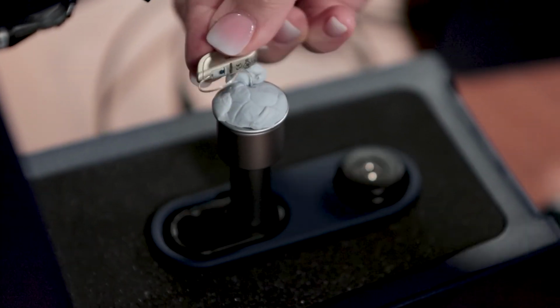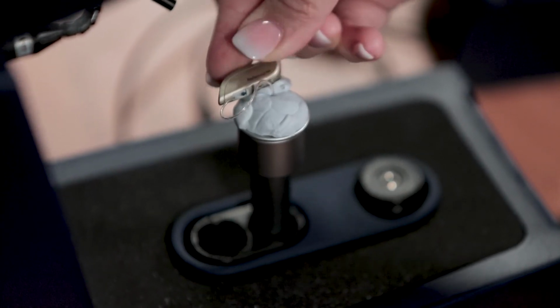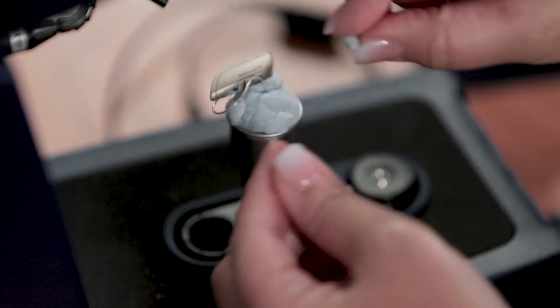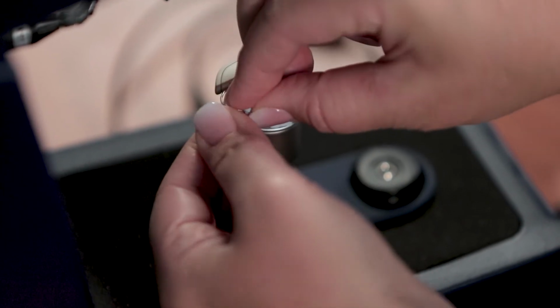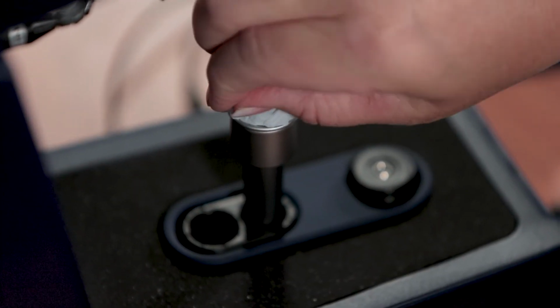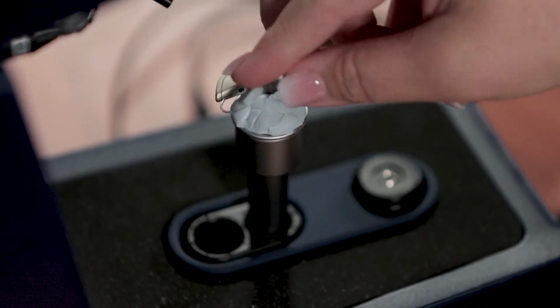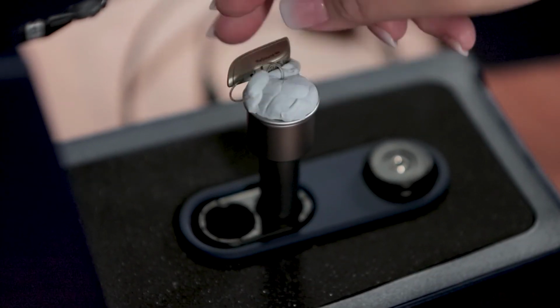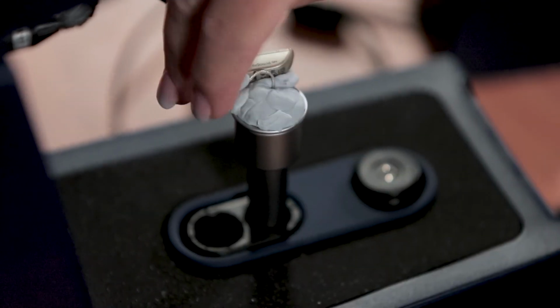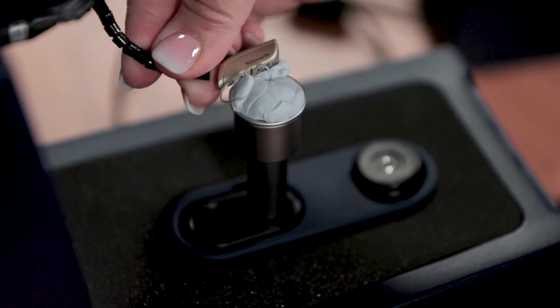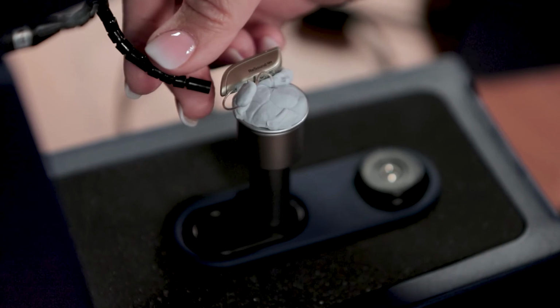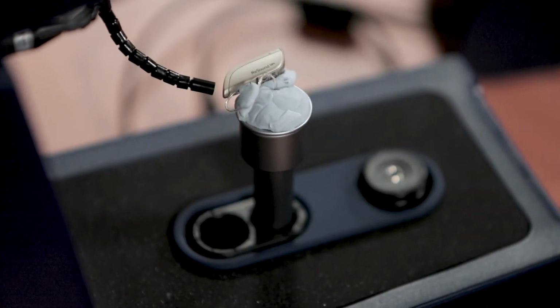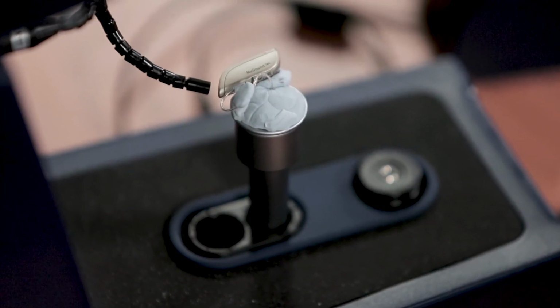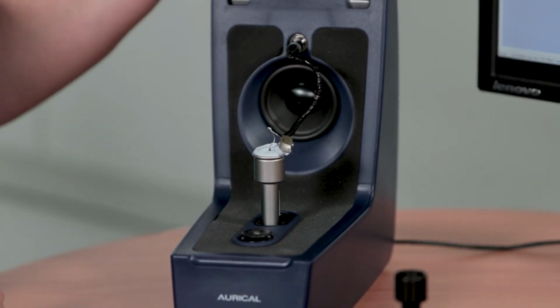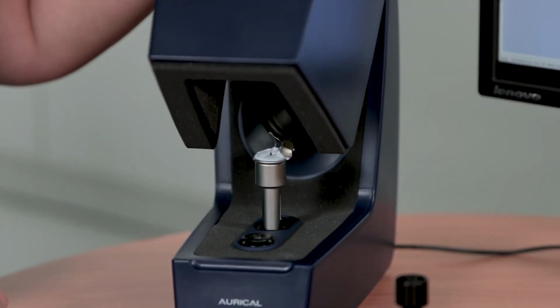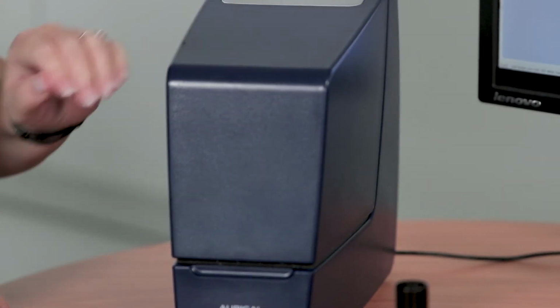Use the small amount of remaining acoustic putty to affix the hearing aid securely to the coupler. If the hearing aid is a thin tube or receiver-in-canal hearing aid, you must also roll a small amount of acoustic putty around the thin tube or receiver wire to remove any potential acoustic artifacts. Position the reference microphone as close as possible to the front-facing microphone on the hearing aid, without touching it, ideally within 5 mm. Ensure the reference microphone is positioned in the middle of the test chamber so that it does not move when you close the lid.